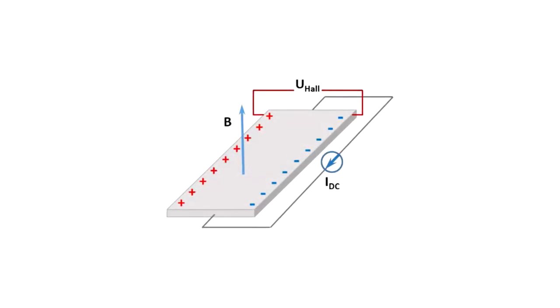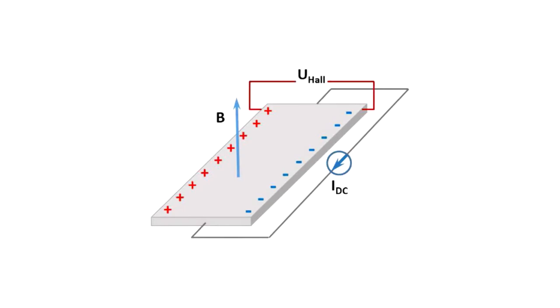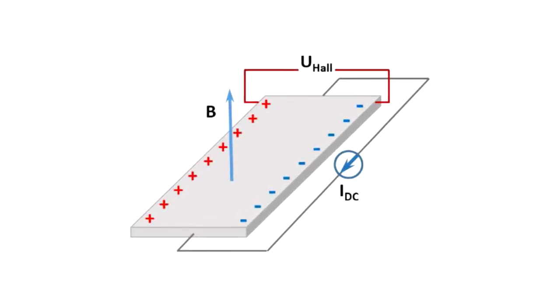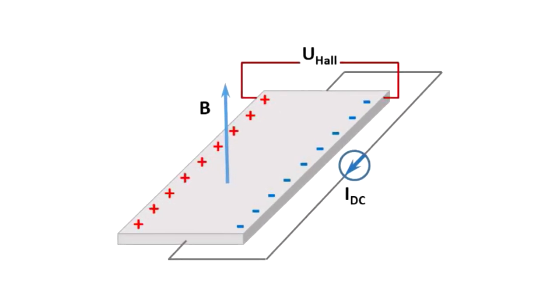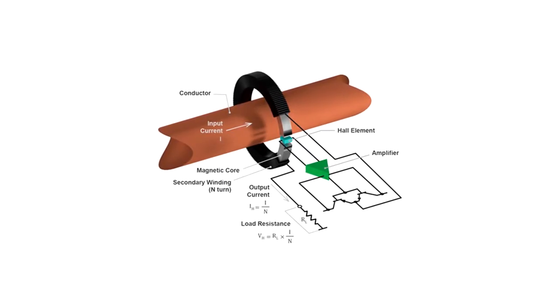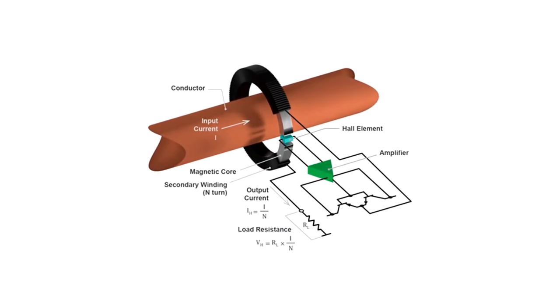The Hall effect is the production of a voltage difference across an electrical conductor when a magnetic field is applied perpendicular to the current. Cheap current clamps cannot measure DC current most of the time because they miss the extra components needed to measure DC.